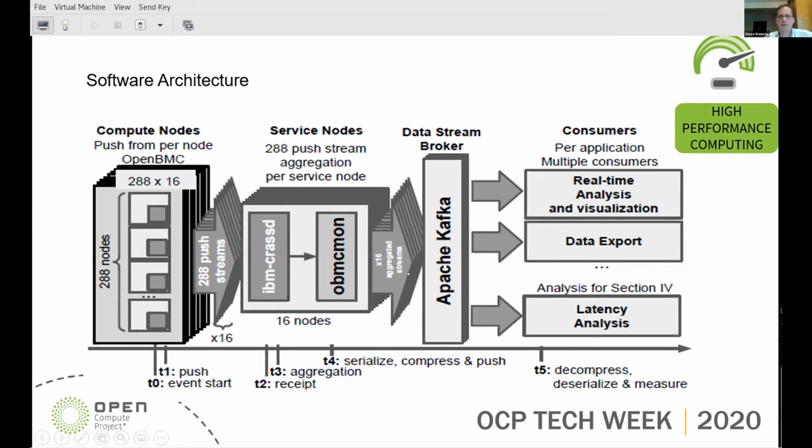Historically, the effort was to go from the left-hand side to the right-hand side as quick as possible and get the data onto persistent store. The scalability of the system and some of the other design parameters for the control systems said that we might not want to wait for an event to go all the way through there. If there's a critical event that implies that a control system's not pumping water into a liquid-cooled rack, I want to know about that before somebody runs a standard query from the data at rest. I want to know about that while the data is in flight.